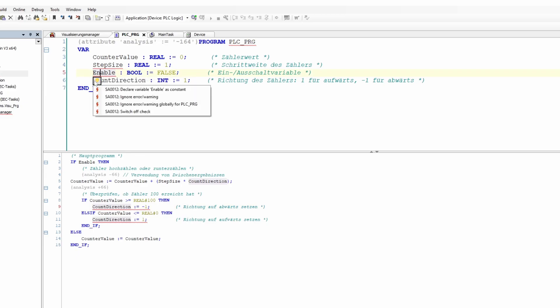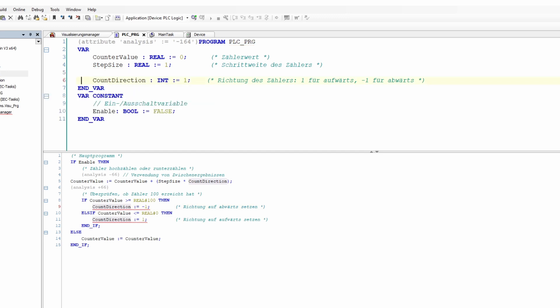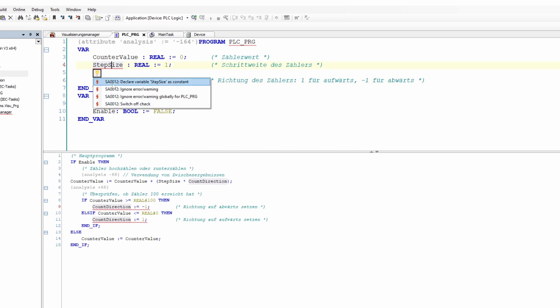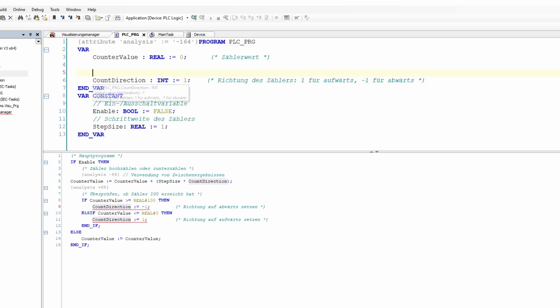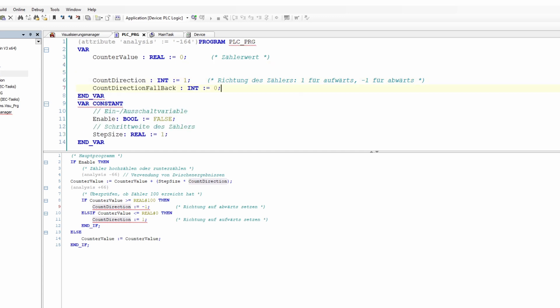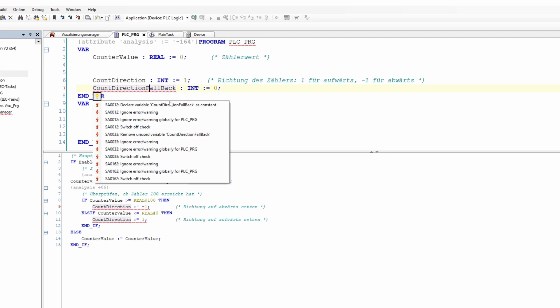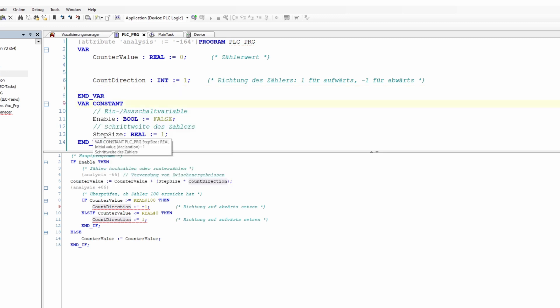CodeSys static analysis is part of the Professional Developer Edition. You can use this tool to check the source code of your application using rules and to find potential problem areas. In the new version, most of these rules are already checked during pre-compilation and reported directly in the editors, meaning you no longer have to compile the project for checking. Quick fixes are also available for many of these rules, so you can have rule violations corrected automatically at the click of a mouse.